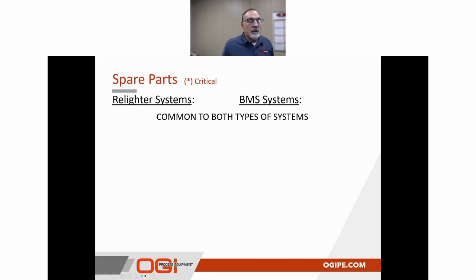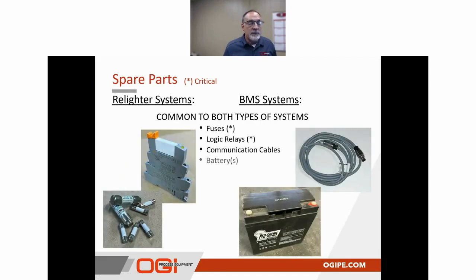Some parts are common to both the relighter and the BMS system, that includes fuses, logic relays, communication cable, and again, here we are back to the battery of both of these systems. Now, the reason that I've got that battery flashing or pulsing is to stress that the battery will not last over the course of multiple years on the shelf. It's best to have a plan that's a part of your PM system to test the load capacity of the battery throughout the year. In this case, before you start your heating season, for example, make sure that battery is in good operating condition and that it can carry a load through the winter.